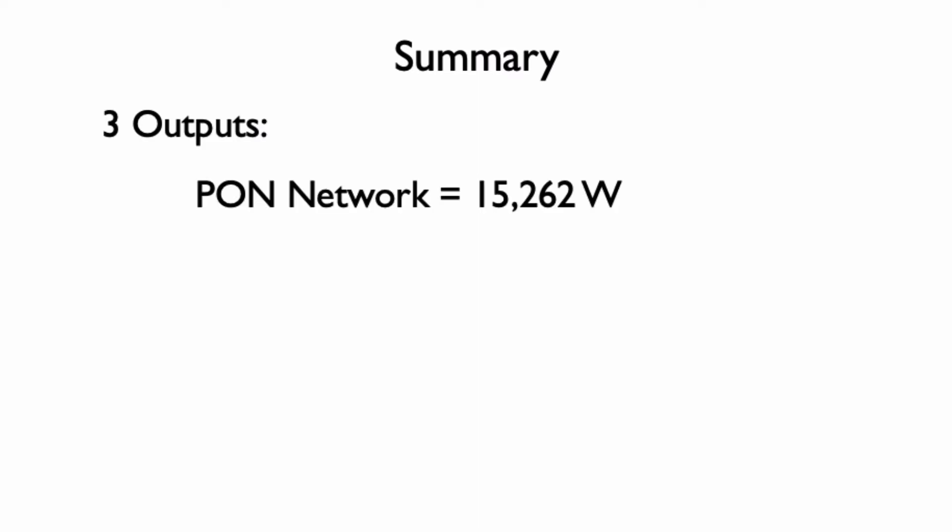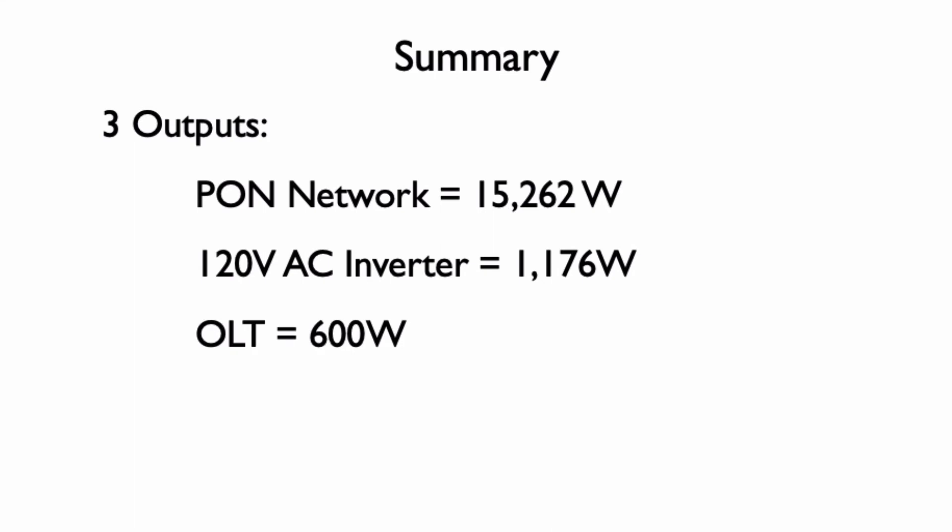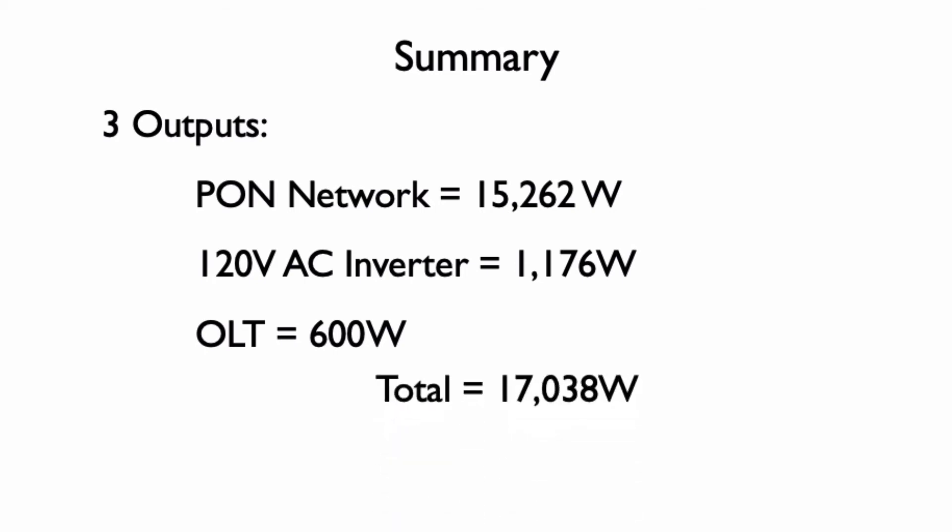Adding up all the power from all three loads we have for the three outputs: the power for the passive optical network at 15,262 watts, the power for the inverter at 1,176 watts, and the power for the optical line terminal at 600 watts for a total of 17,038 watts.